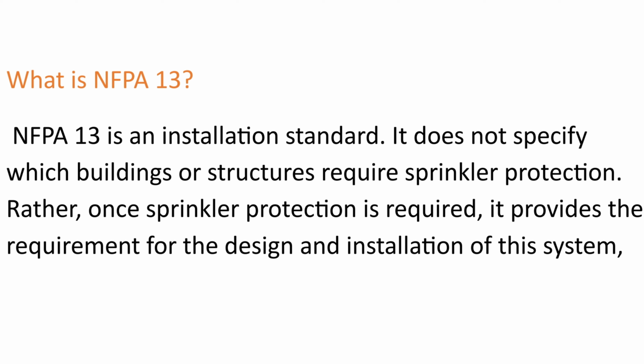What is NFPA 13? NFPA 13 is an installation standard. It does not specify which buildings or structures require sprinkler protection. Rather, once sprinkler protection is required, it provides the requirements for the design and installation of the system.